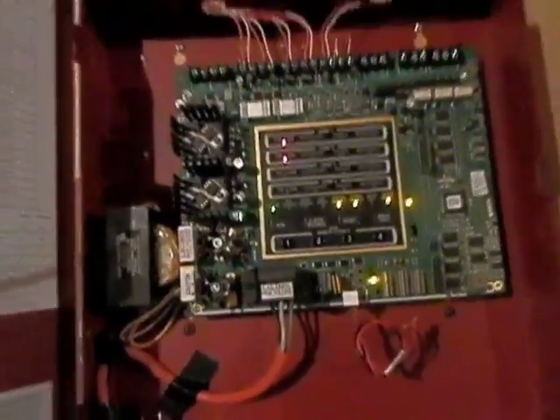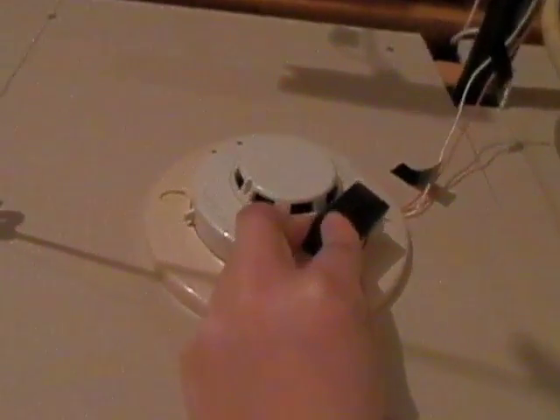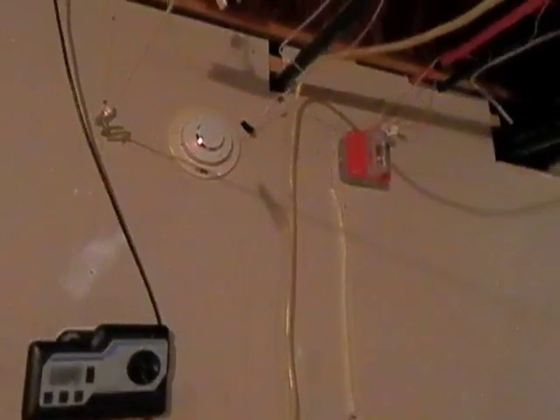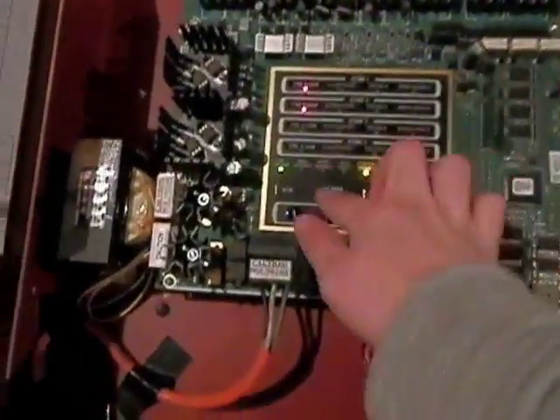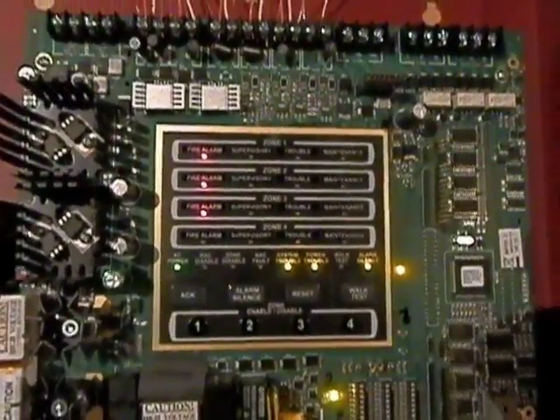All right, and now the final part of the test — we're going to set off the smoke detector with my magnet here. So I'll go ahead and set my keys down and do zone 3. You can see we got an alarm in zones one, two, and three.